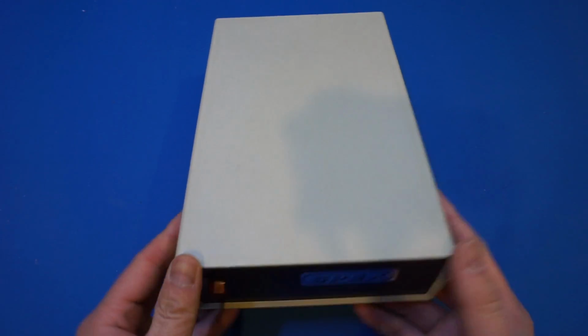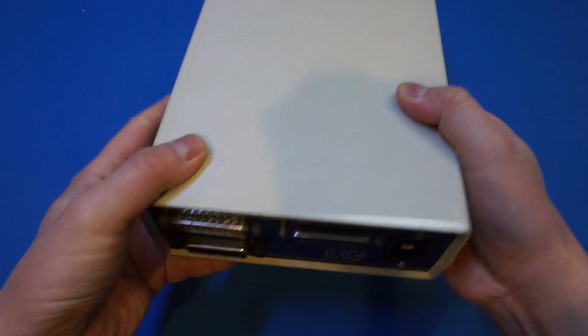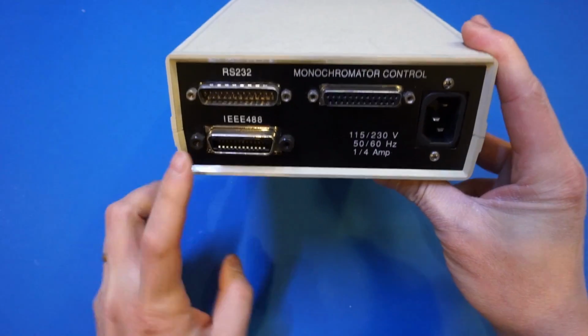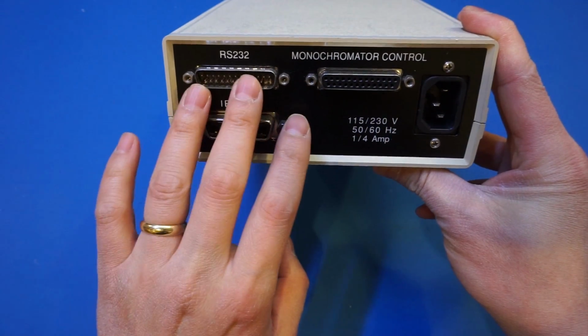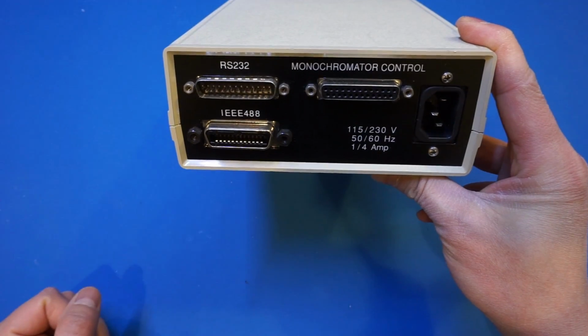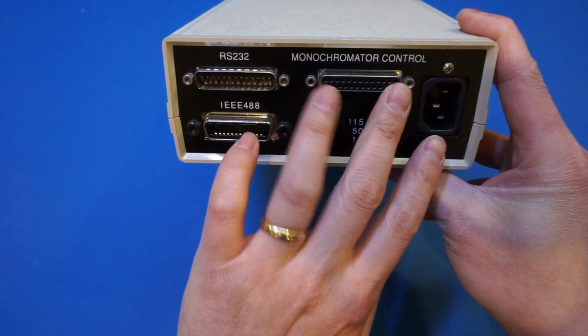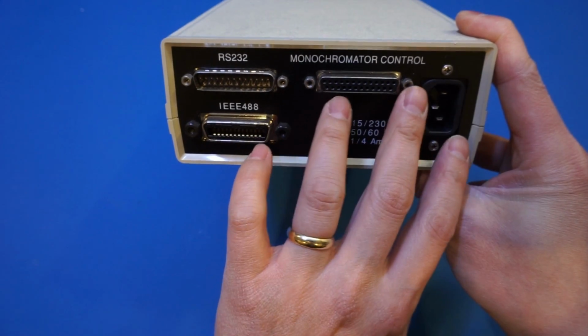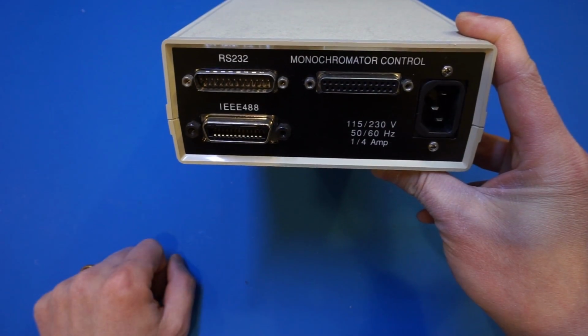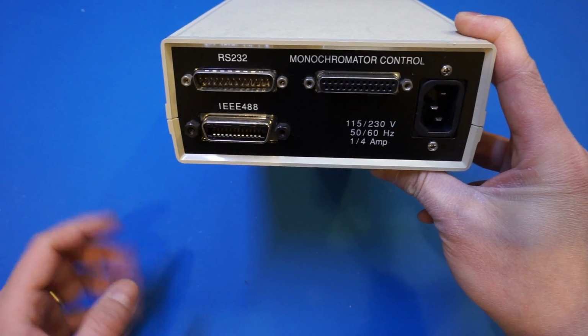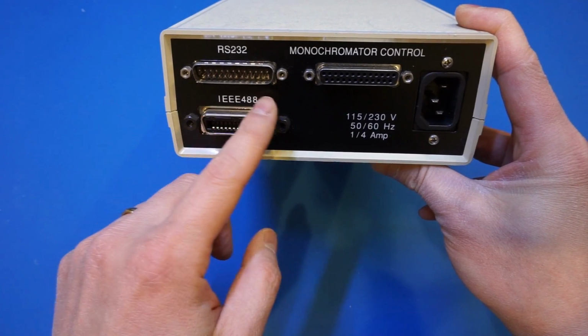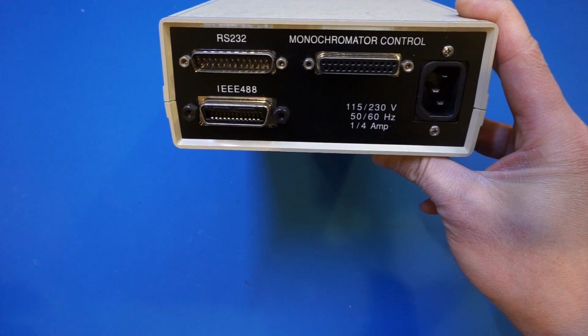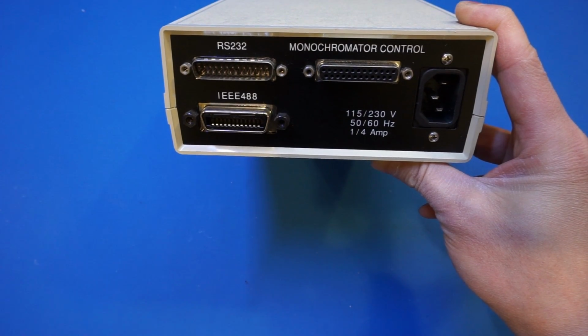Let's shift our attention to this main control unit, and let's flip it over. You can see that from the back, we have three ports here. One is the RS-232, which connects to that keypad module. We also have a female port, which is also an RS-232. This one goes to your monochromator control, which we don't have here. But we also have an HP-IB, the IEEE-488 port, which you can use to hook up to your computer. That's pretty much all we have on the outside of this unit.